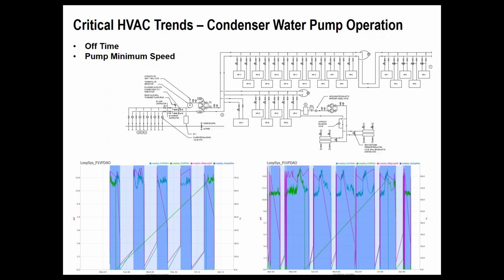If all zones are satisfied and no compressors are operating in the heat pumps, we don't need the pumps on. So I needed to do a check to see whether we really have that in the programming, or whether you are just running those pumps at minimum all the time. On the left lower graph, we can see the pumps turning on and off on a daily profile. On the right, the heat pumps are having to work a bit more, so we still see a daily profile, but the heat pumps are working more, though they still turn off for some number of hours in the middle of the night.